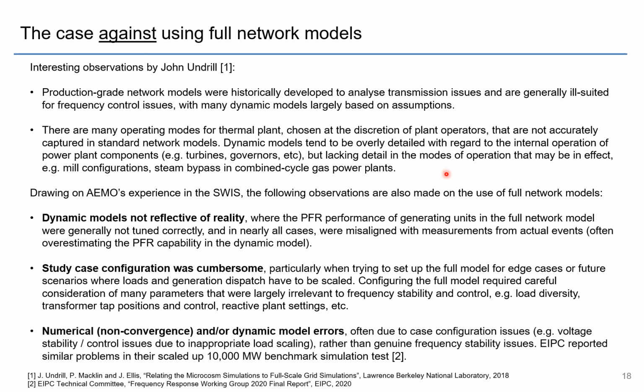And finally, we found there was quite a lot of numerical non-convergence errors and dynamic model errors. And often this was due to the case configuration issues. So if you inappropriately scaled loads, if you didn't consider diversity properly, or you didn't set your reactive plant, you could have voltage stability and control issues. And so these are issues that are not frequency stability related. And EIPC reported similar problems when they tried to scale up the EI model for a 10,000 megawatt benchmark simulation test.